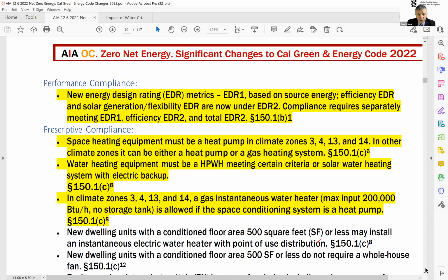In climate, you can use gas, and in climate zones 3, 4, 13, 14, you can use instantaneous water heaters, maximum of 200,000. By the way, 200,000 is actually 199,000. Why do they call them instantaneous at 199,000? Because at 200,000, the definition becomes a boiler, and once you have a boiler, you have to have a 1-hour rated room.